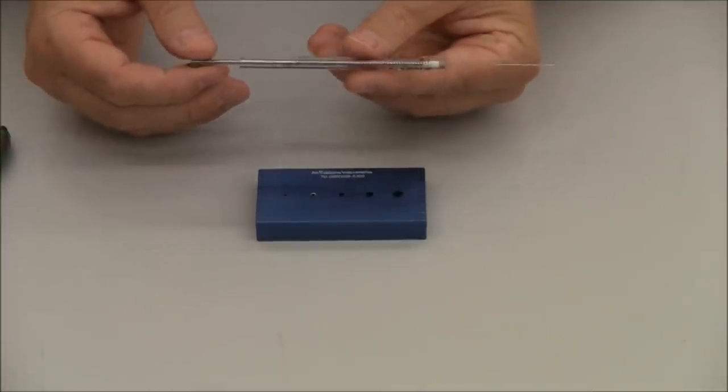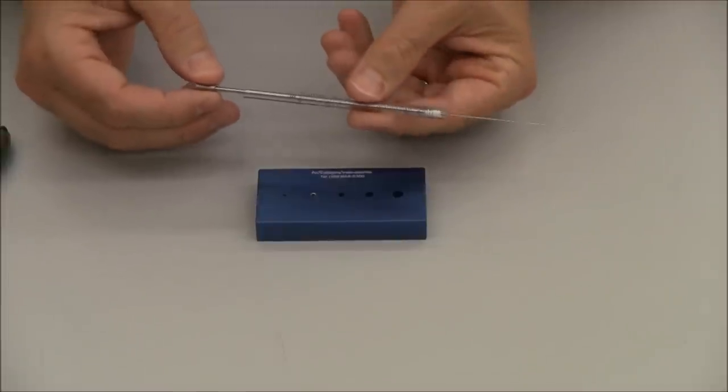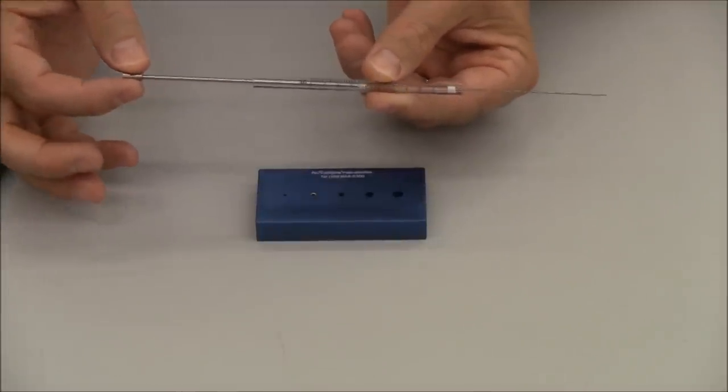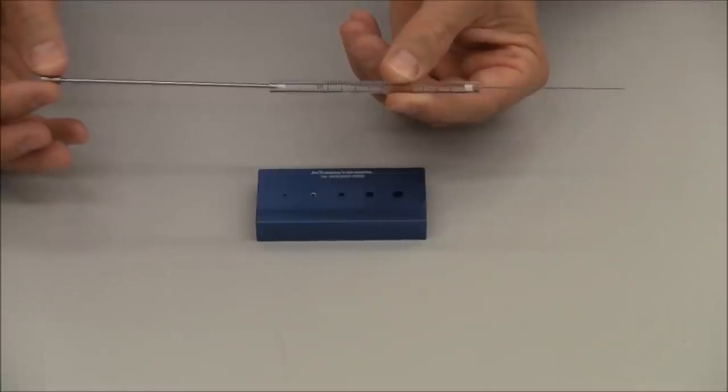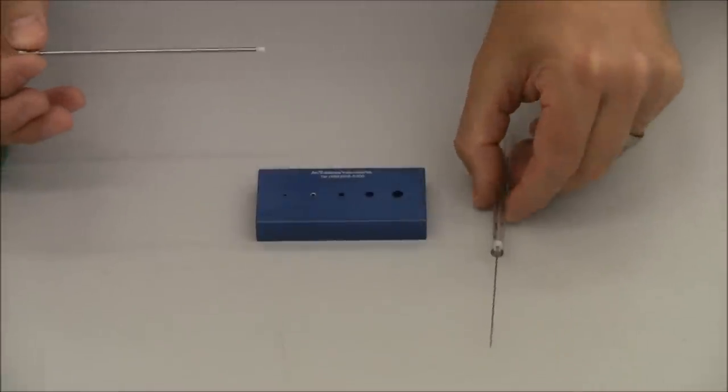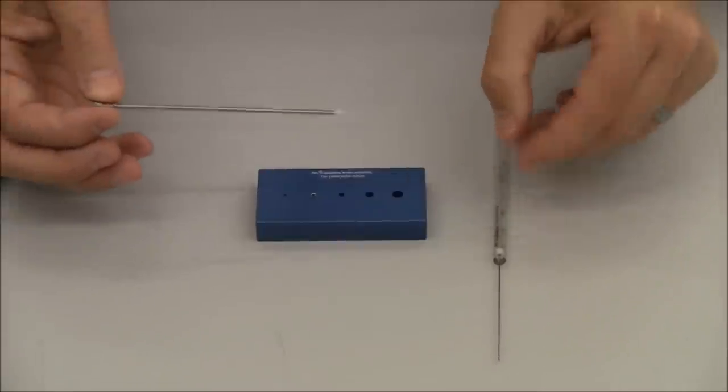Changing a Teflon tip on a multi-syringe. Pull out the barrel very carefully, syringe down, be careful that it doesn't fall off your desk.